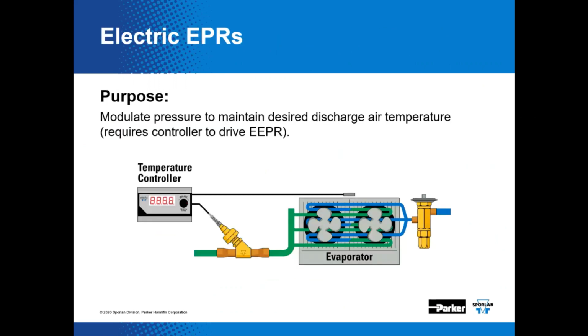In comparison to the EPR, this option requires a controller to accept the discharge air temperature reading from a sensor. The controller then positions the EEPR. By stepping the EEPR in a closing direction, the pressure will increase and cause the discharge air temperature to also increase.